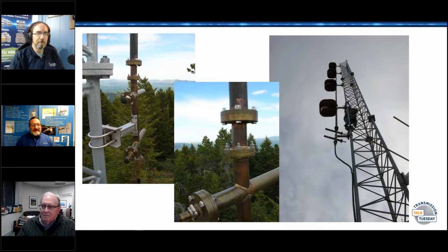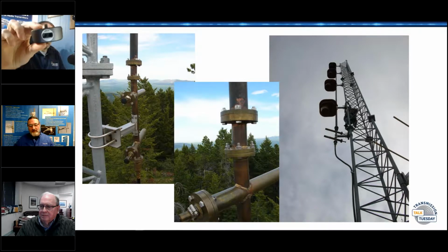Taking the time to just check, especially after an event like a weather event, is important. So the other thing, Gary, you mentioned doing a visual inspection. If there's some indication something's going bad, thermal imaging is a lot more accessible today. That's a great tool to find burned up connections, which often start because of loose connections, not necessarily excessive voltage - though that could be causing excessive voltage in another part, a quarter wavelength away.